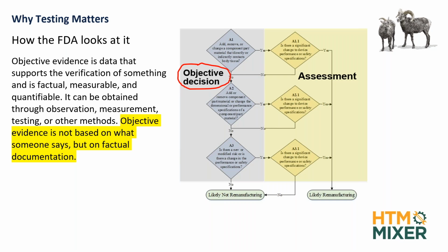So here's what the FDA did. They came out with the remanufacturing document. They gave flow charts that allowed people to make objective decisions. I won't go too far into this, but I know it's really small. You can read it later. So A1 right up in here says, add, remove, or change a component, part, material that directly or indirectly contacts body tissue. Okay. Does it? Yeah. Then you have to go over here. Is there a significant change to device performance or safety specifications? If it is, you see these are all going to say that's likely remanufacturing. You have to file a 510K for it.